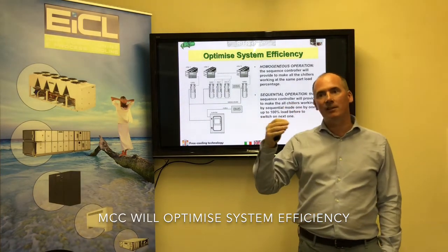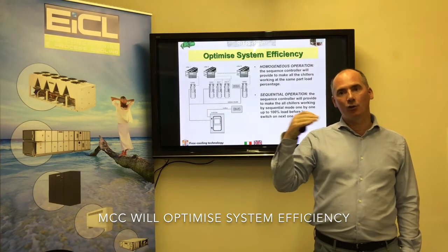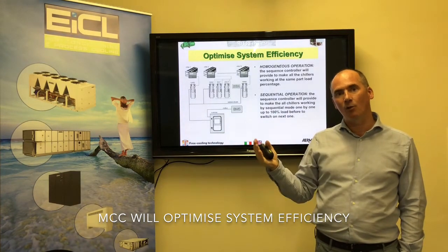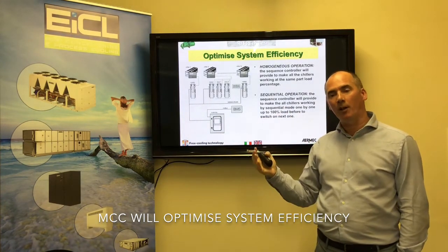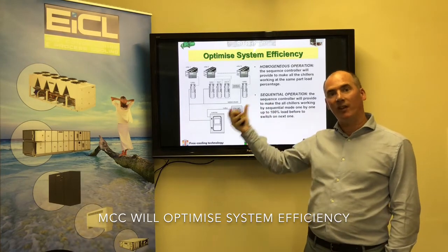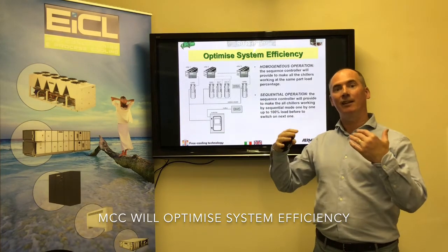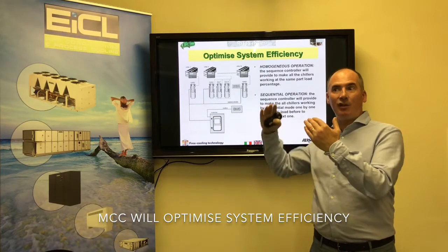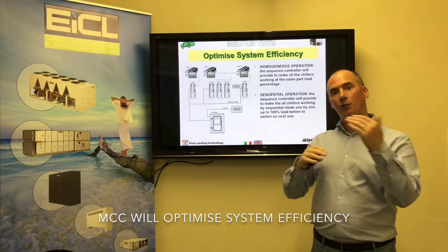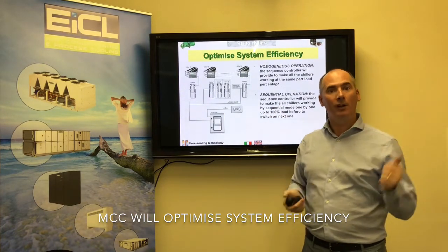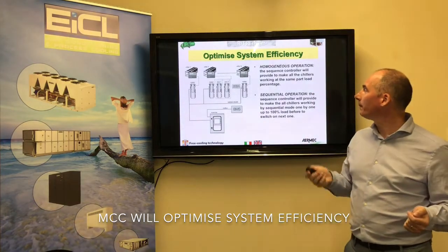And it understands, let's say when you have a scroll chiller and it's getting up to 70% load, and we know the efficiency is dropping off, it will then decide to enable the second chiller and run the two of them at, say, 35%. So instead of having an EER dropping off to 3, you might have 2 chillers running with an EER of 4. So obviously it's far better to do it that way.